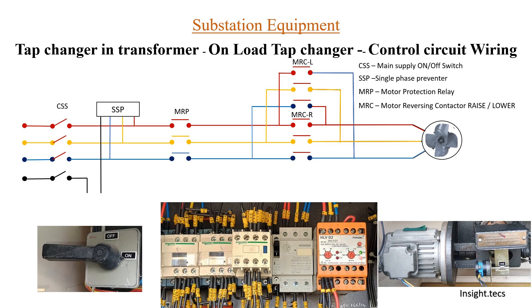In the previous video we already saw the power circuit of the tap changer. We saw these two contacts, MRCL and MRCR, for raising and lowering of the tap. We saw how this entire power circuit works, and this is the motor. To rotate this motor, these two contacts are main, and these contacts get the command from the control circuit.